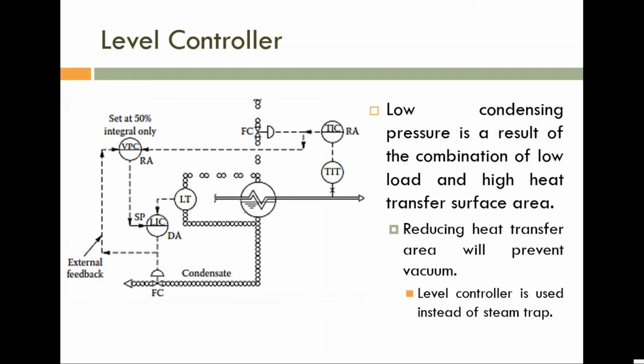So here, first consider the first instrumentation that we discussed, the manipulation of steam flow rate or steam throttling case. So why does it have the blown up problem? If it has low load and low operating temperature, because due to the sudden variation of heat transfer area, a small pressure is created. So for a time being, liquid is trapped inside the heat exchanger. So due to that, liquid head will increase. So suddenly that one is removed. So due to the sudden variation of heat transfer area, the blown up problem occurs.